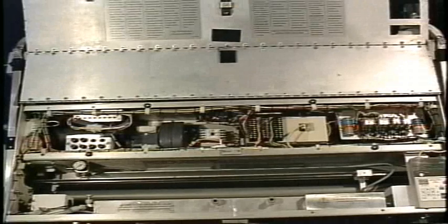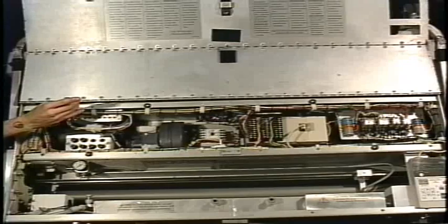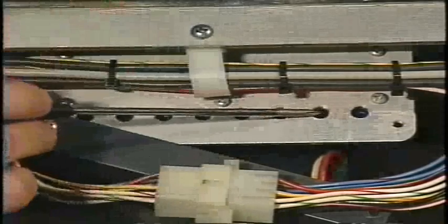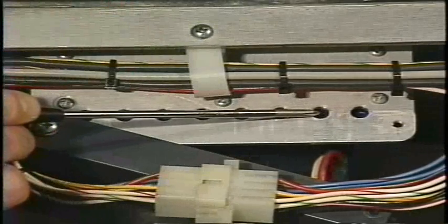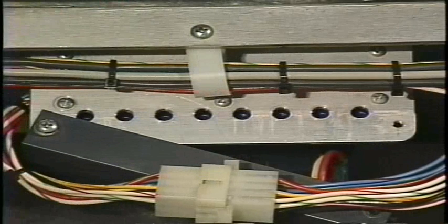If we need to raise or increase a drive speed, we would turn the small trim pot inside with a precision screwdriver clockwise. To decrease that speed, we would go counterclockwise. In the event that we would adjust the range, it would be the opposite. Counterclockwise would increase the speed, and clockwise would decrease.